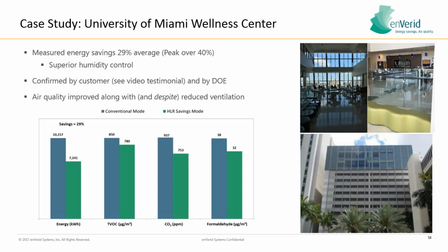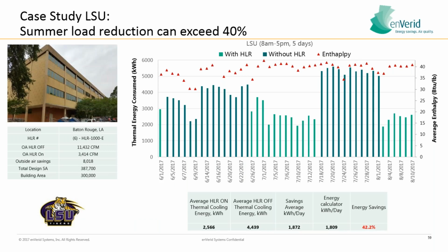Just because we're reducing outside air doesn't mean that we're compromising on indoor air quality. In this particular case, you can see that we were reducing outside air. We saw a peak savings of over 40%, and total VOCs, CO2, and formaldehyde all decreased. So even though we were reducing outside air and seeing massive energy savings, indoor air quality improves.